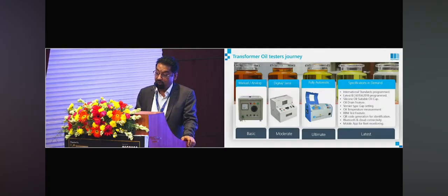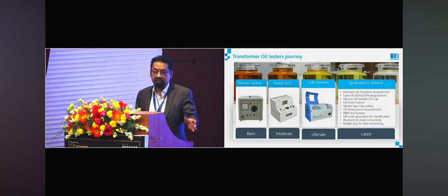Now people want all the international standards to be programmed in the oil BDV testers, and after selecting the standard, the rate of rise of voltage, stand time, and stirring time should be adjusted automatically. They are also looking at the latest changes in standards, like IEC 60156, which has changed twice. Now the 2018 standard is the latest, and they are demanding that it be programmed.